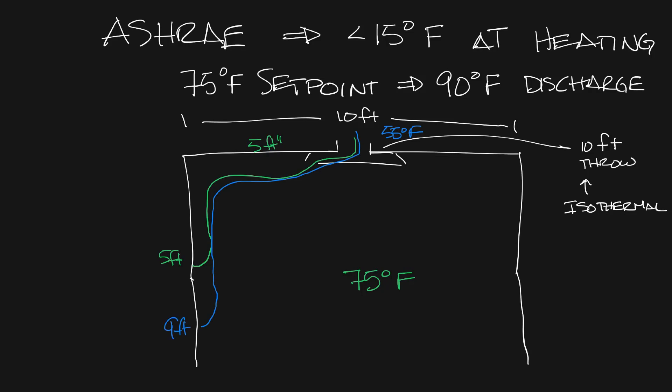Now in heating you have the opposite condition, the throw is going to shorten. So let's go to our 15 degree delta T or 90 degree supply air condition. In this case the throw will go down to about 6.6 feet and so it's going to go down about a foot and a half down the wall.